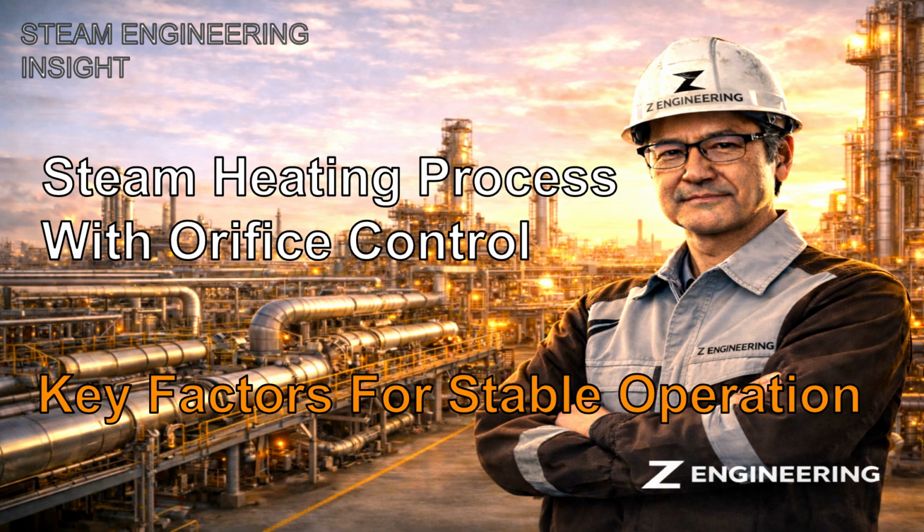In the previous video, we discussed the conditions where orifice traps do not work. Condensate flow becomes unstable, or differential pressure becomes unstable. When either of these conditions collapses, the orifice principle no longer holds. So the next question is simple. What kind of heat exchangers allow an orifice trap to work properly? Today, I will explain this using real examples.